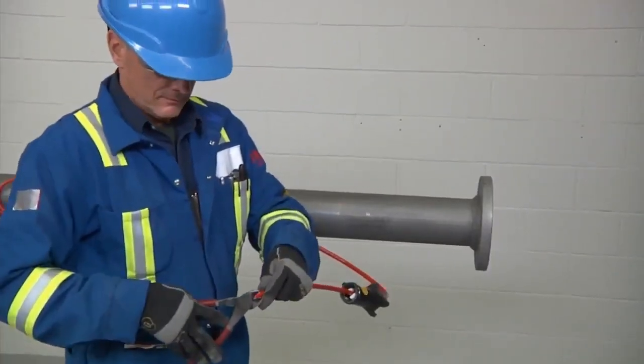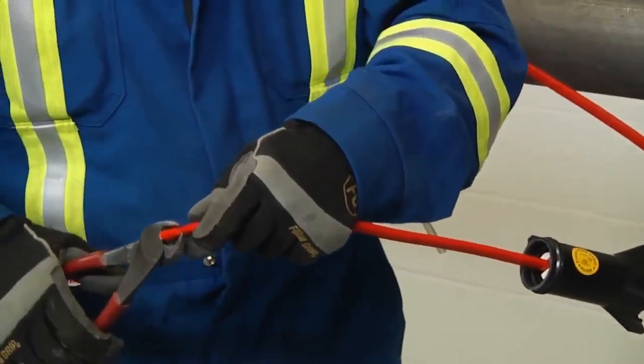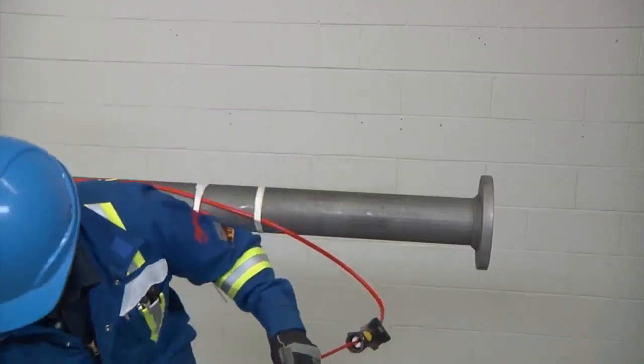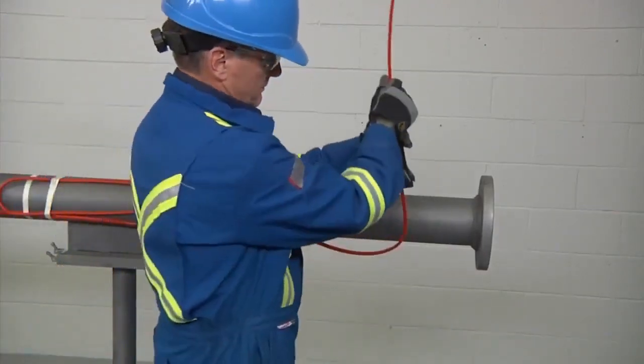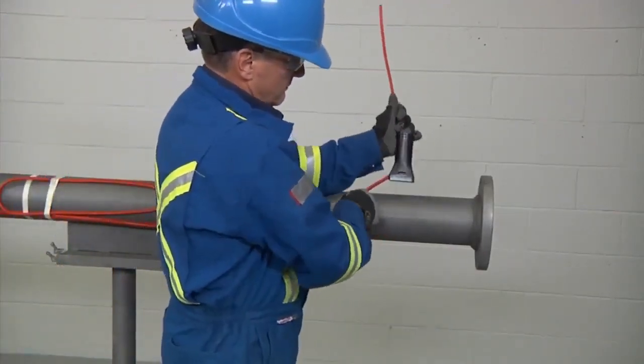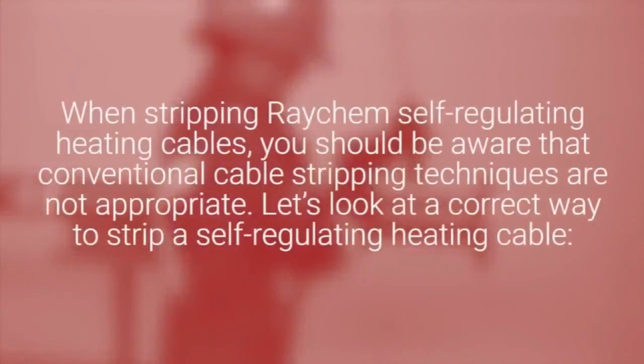Now, square off the cable end with a 90-degree cut, but do not attach to the pipe yet, and proceed to stripping the end of the cable. When stripping Raychem self-regulating heating cables, you should be aware that conventional cable stripping techniques are not appropriate. Let's look at a...